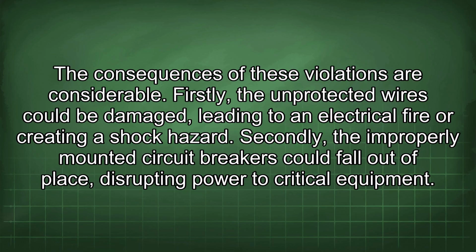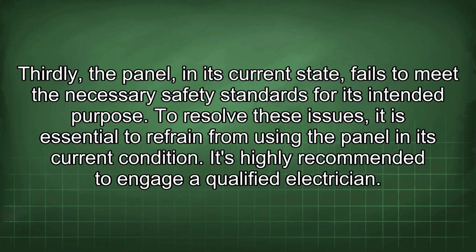Firstly, the unprotected wires could be damaged, leading to an electrical fire or creating a shock hazard. Secondly, the improperly mounted circuit breakers could fall out of place, disrupting power to critical equipment. Thirdly, the panel, in its current state, fails to meet the necessary safety standards for its intended purpose.